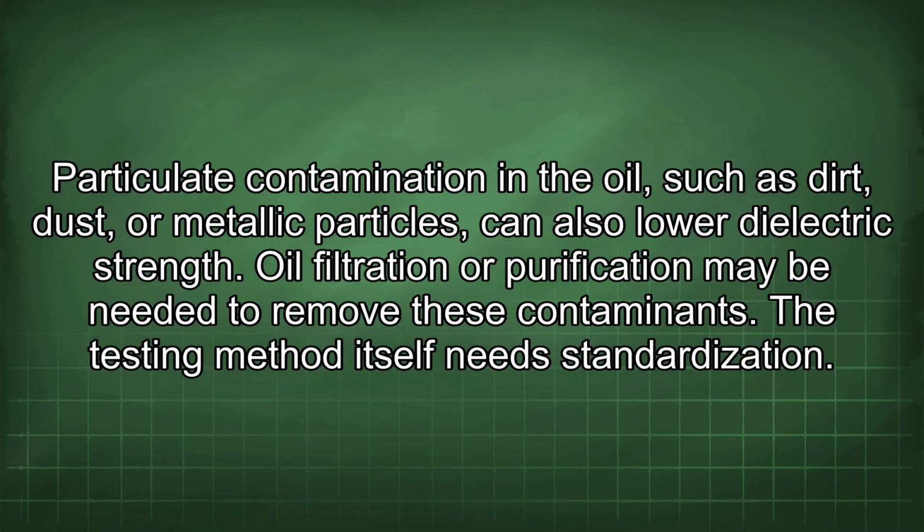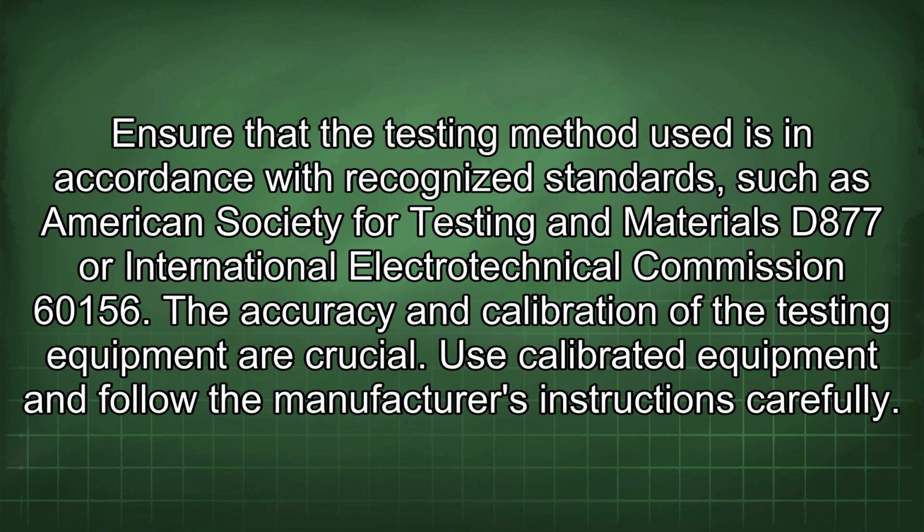Particulate contamination in the oil, such as dirt, dust, or metallic particles, can also lower dielectric strength. Oil filtration or purification may be needed to remove these contaminants. The testing method itself needs standardization. Ensure that the testing method used is in accordance with recognized standards such as American Society for Testing and Materials D877 or International Electrotechnical Commission 60156.